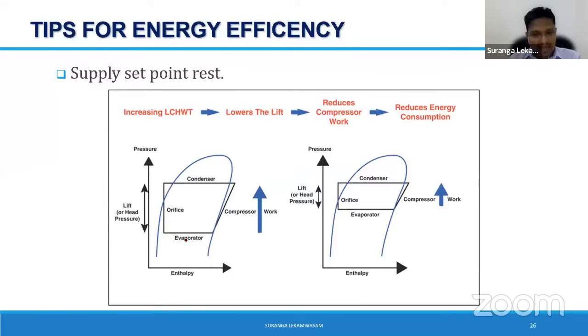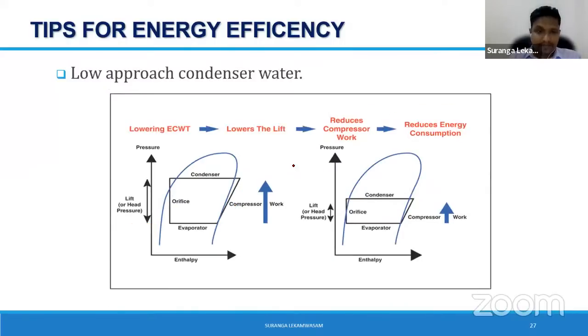Then what will happen? You can understand just by seeing the p-h diagram. This was your 7 degrees set point. This is now your reset value, maybe let's say 8 degrees or even 7.5 degrees. Now your chilled water supply temperature has increased, and thereby you can see the compressor work now reduces. So your chiller efficiency is substantially improved. So automatic supply set point adjustment is something you can look at very smartly, right? That is something you should look at.